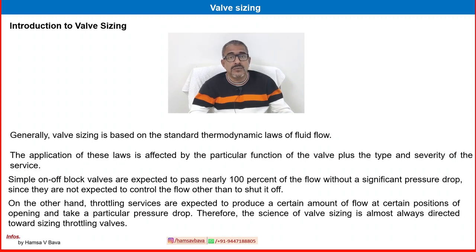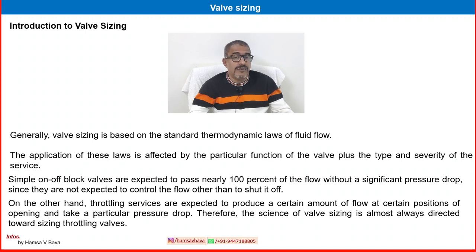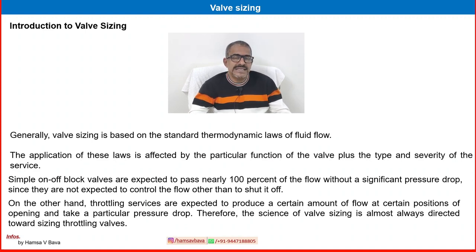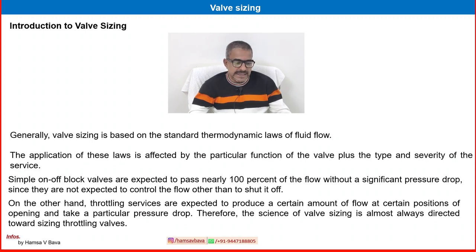On the other hand, throttling valves are expected to produce a certain amount of flow at certain positions of opening and take a particular pressure drop — unlike on-off valves. We have already studied the differences between control valves, isolation valves, and manual valves. Therefore, the science of valve sizing is almost always directed towards sizing of throttling valves.